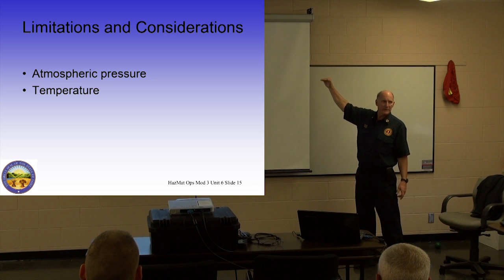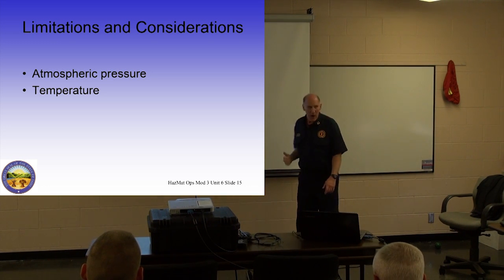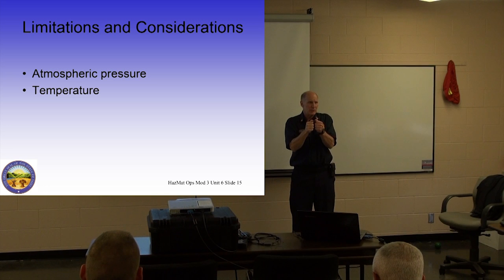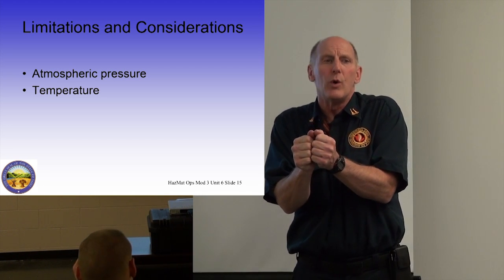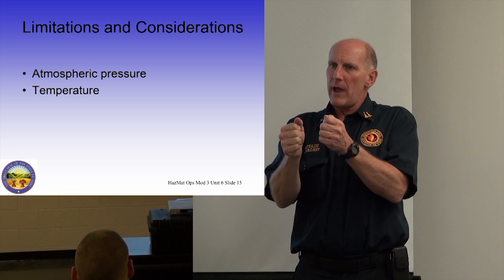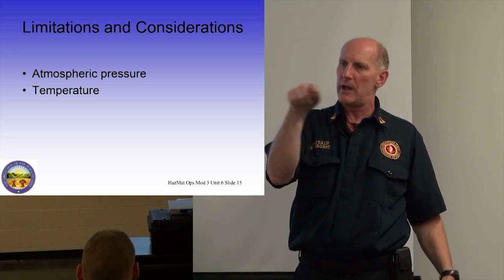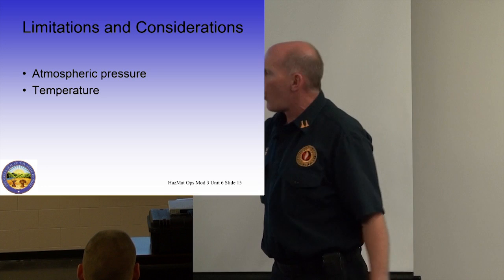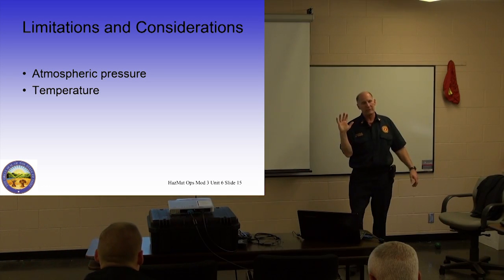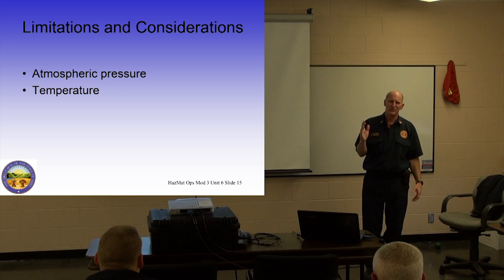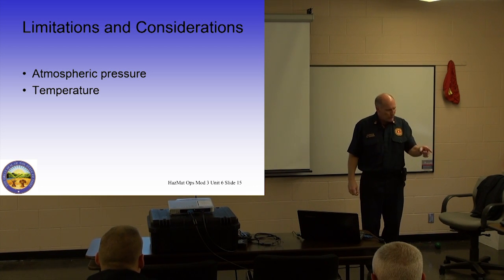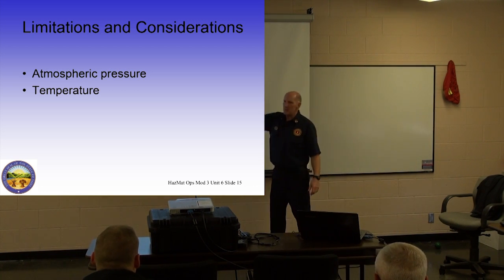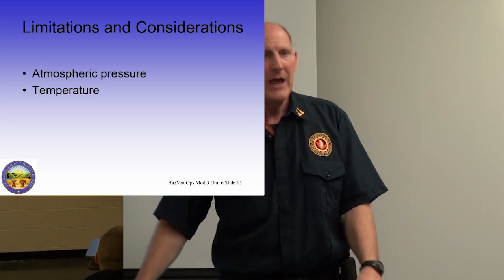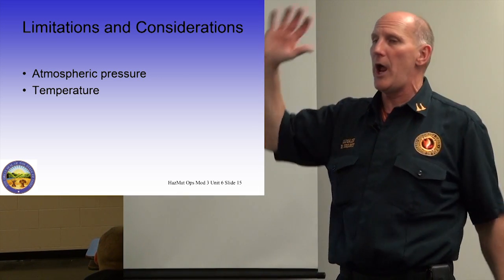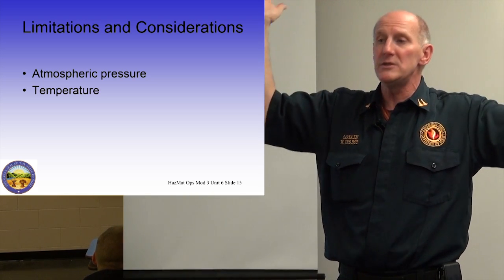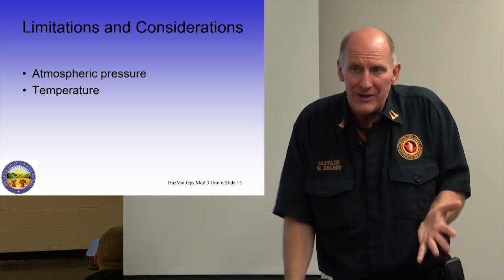But there's problems with that program. And the reason there's problems is because if I take that chemical sensor into a cold atmosphere, the cold atmosphere is also going to make the two chemicals react slower. And so a cold atmosphere could tell you, well, there's low O2, but there's really not low O2, it's cold. If you read your directions, it'll tell you there's a temperature that the O2 sensor will freeze. And when it freezes, you don't get a little indication, hey, I'm frozen and not accurate. It just freezes at whatever level it is giving you, and you don't get a change.